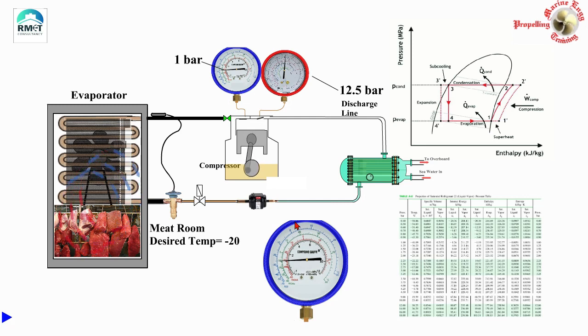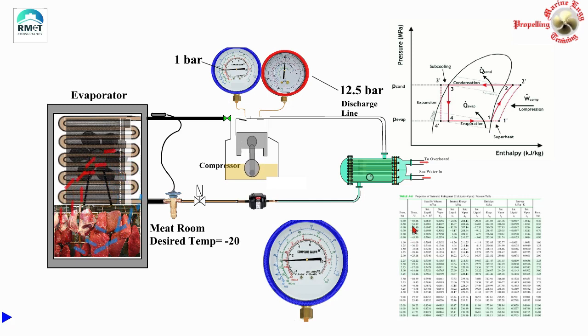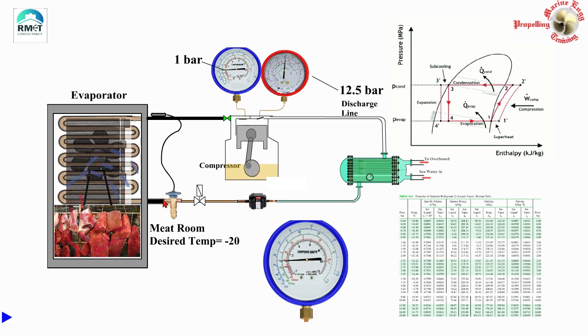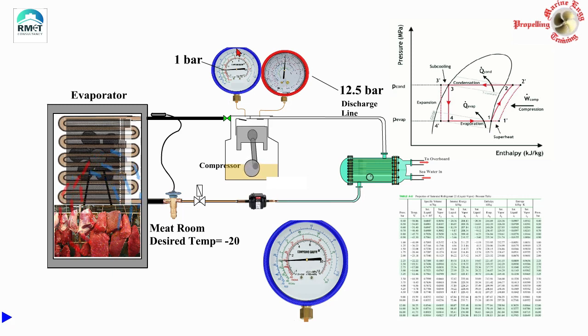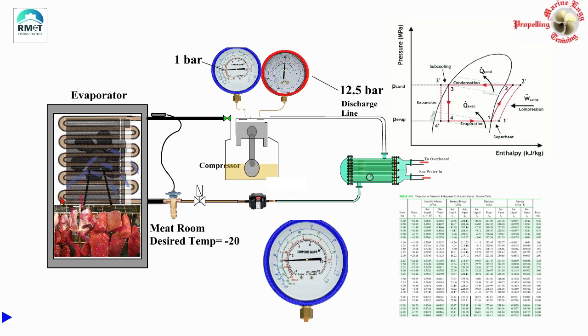In the previous videos we saw the basics of the refrigeration system and how to read the saturation pressure and temperature table. We also learned that if the desired cold room temperature should be minus 20, then the liquid freon after crossing the expansion valve will drop its temperature down to almost minus 25, and to a corresponding saturation pressure of 1 bar, which can be read on the suction gauge. This liquid freon at minus 25 travels up the evaporator, gradually changing its state to refrigerant gas, thereby absorbing the heat from the meat room.